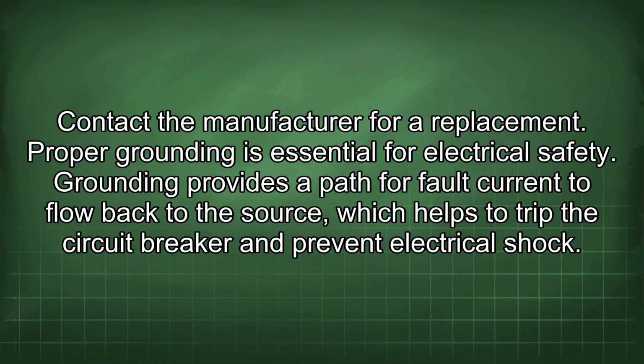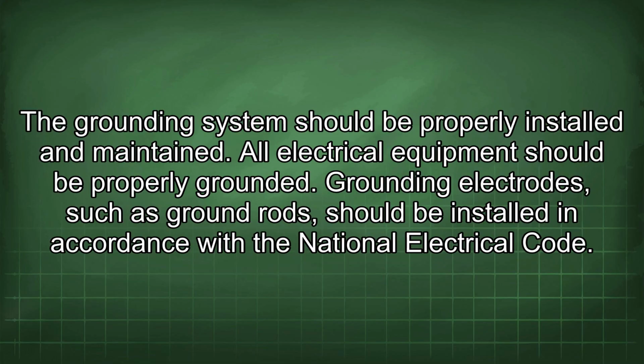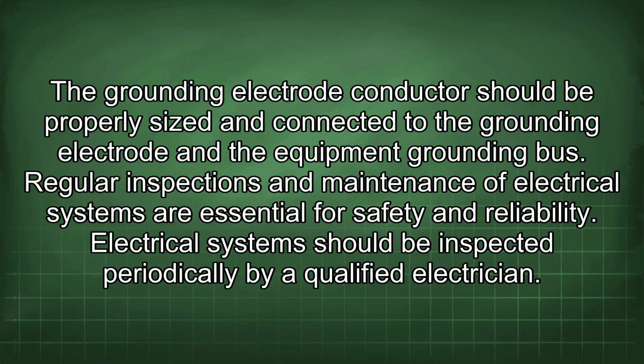Proper grounding is essential for electrical safety. Grounding provides a path for fault current to flow back to the source, which helps to trip the circuit breaker and prevent electrical shock. The grounding system should be properly installed and maintained. All electrical equipment should be properly grounded. Grounding electrodes, such as ground rods, should be installed in accordance with the National Electrical Code. The grounding electrode conductor should be properly sized and connected to the grounding electrode and the equipment grounding bus.